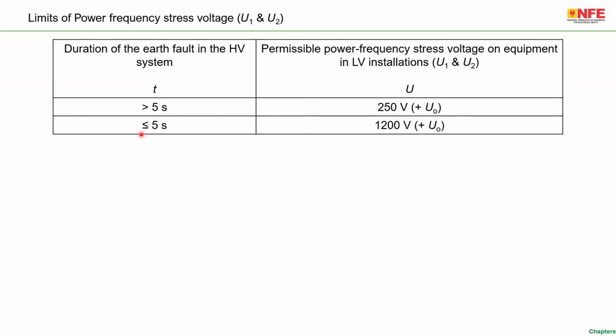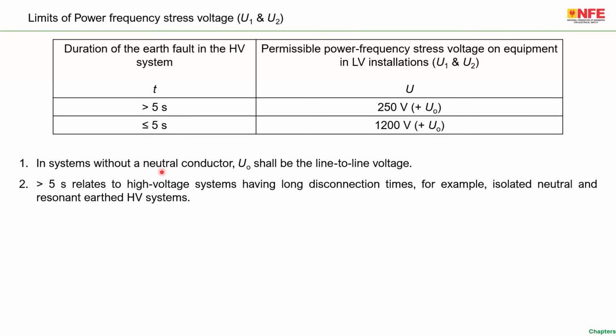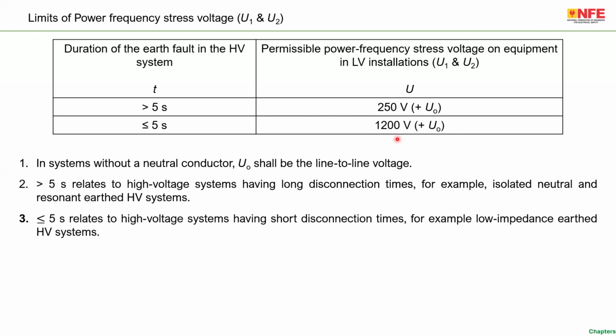Now, the tolerable limit of stress voltage. Here, there are two systems considered: less than or equal to 5 seconds, and greater than 5 seconds. This means the disconnection time of the high voltage side of the transformer in case of a fault on the high voltage side. There are two times explained here: solidly earthed system, less than or equal to 5 seconds. Impedance earthed system, more than 5 seconds. In a solidly earthed system, 5 seconds means the maximum stress voltage has to be limited to less than 1200 volt. You can find it again in the standards 61936, IEC 60364, as well as IS 732.